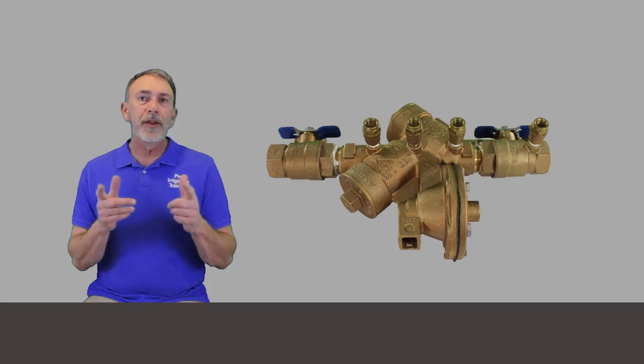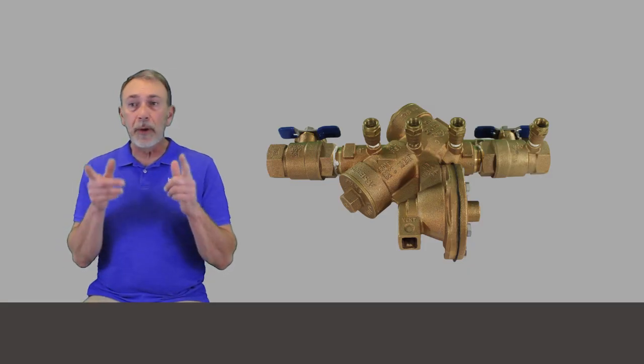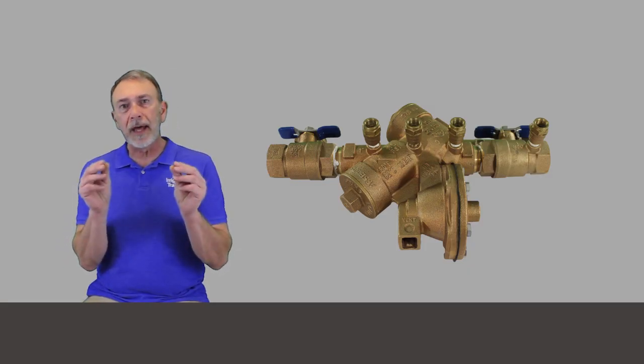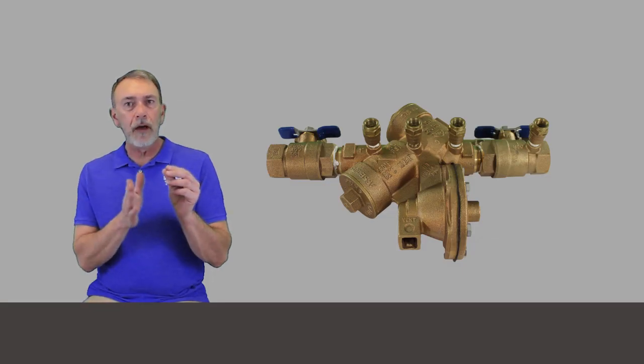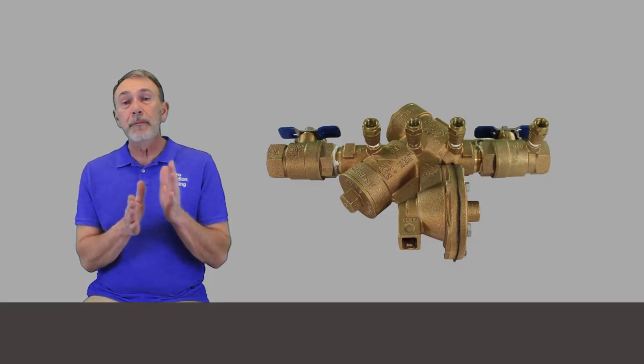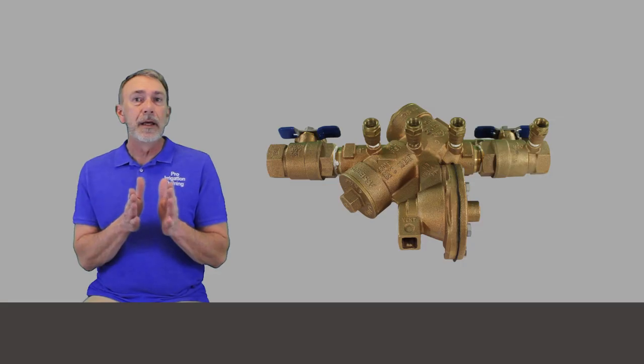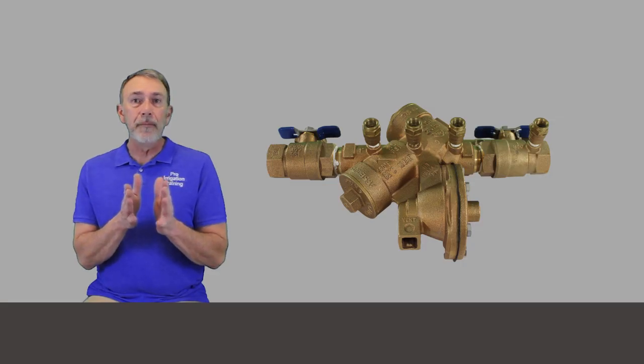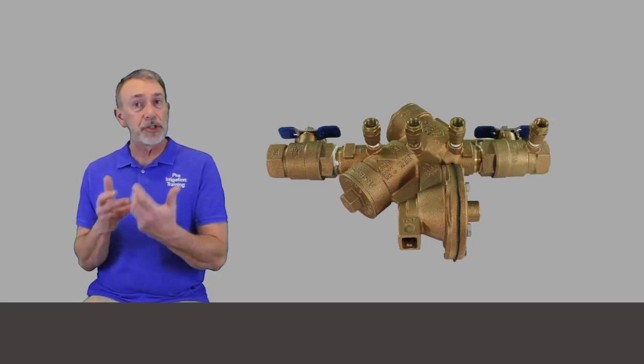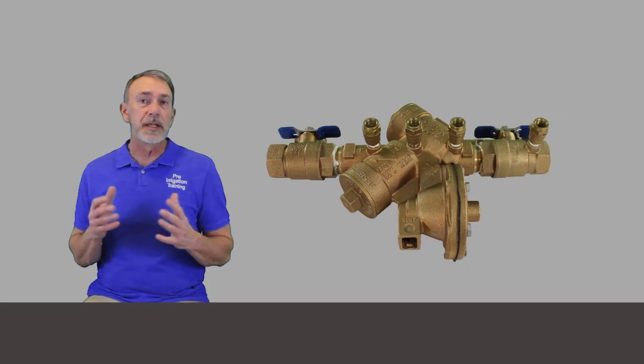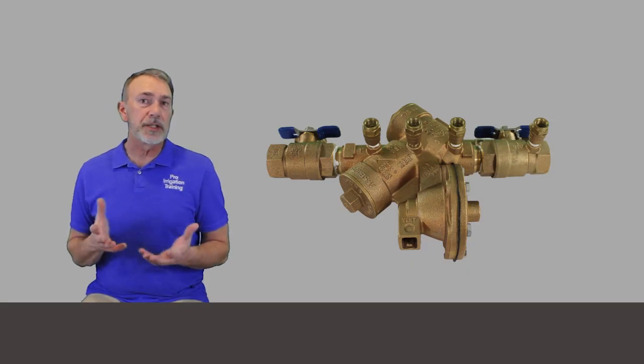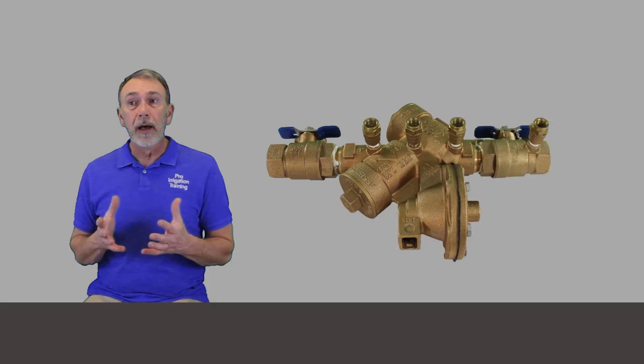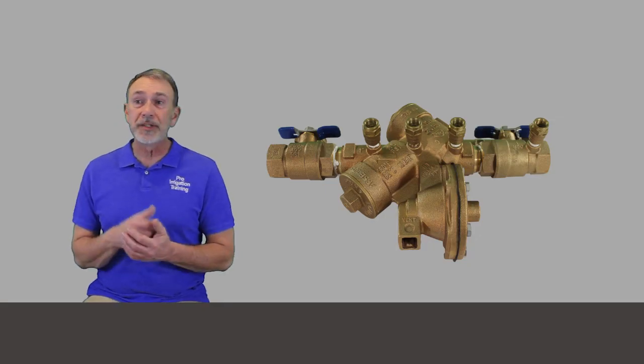We'll talk about it more in an individual lesson, but it can protect against both back siphonage and back pressure. But what's wild about the RP is that if both of your check valves get fouled out, the relief valve in between should be able to maintain the device's ability to stop backflow.